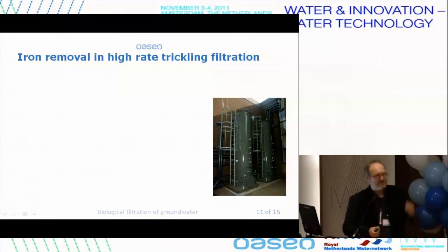Now I go to a more extreme system, trickling filtration. The general perspective is that these Gallionella really grow under low oxygen conditions. In trickling filtrations, you aerate a lot, and the water coming out is oxygen saturated, so it has really high oxygen content. The pH is about 7.4 in these cases. So, at first glance, you would not expect much biological iron oxidation.